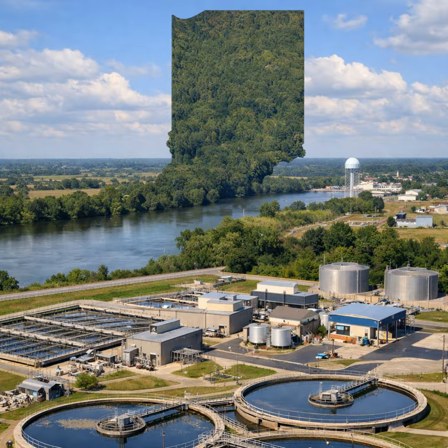Mixed liquor volatile suspended solids, or MLVSS, is the amount in milligrams per liter of organic or volatile suspended solids in the mixed liquor of an aeration tank. The volatile portion is used as a measure or an indicator of the microorganisms present. So that's what mixed liquor volatile suspended solids is.